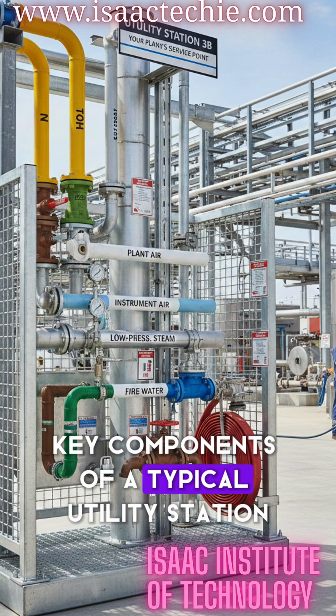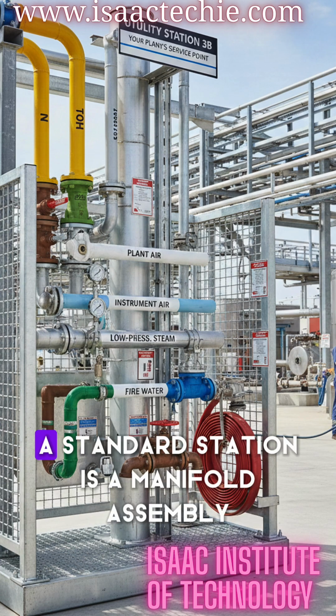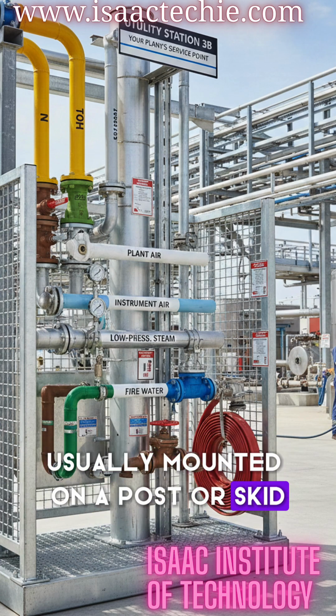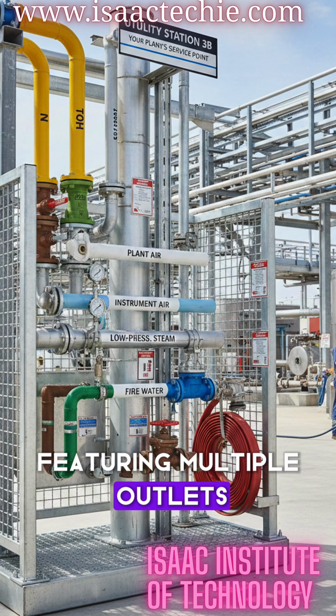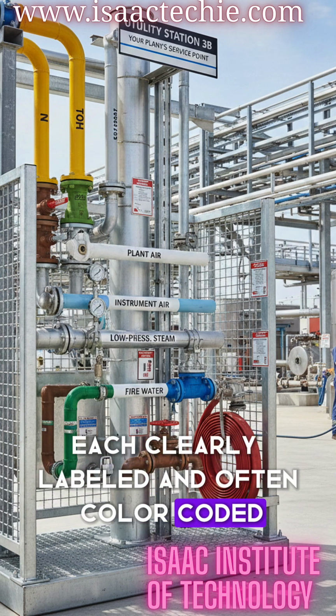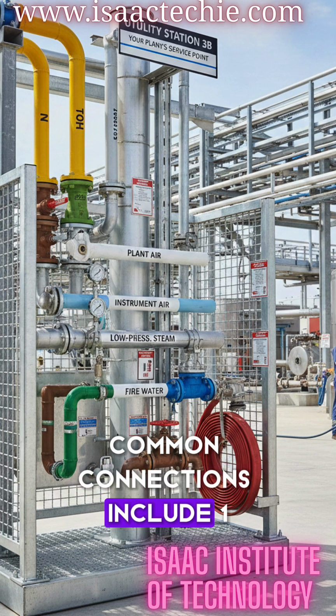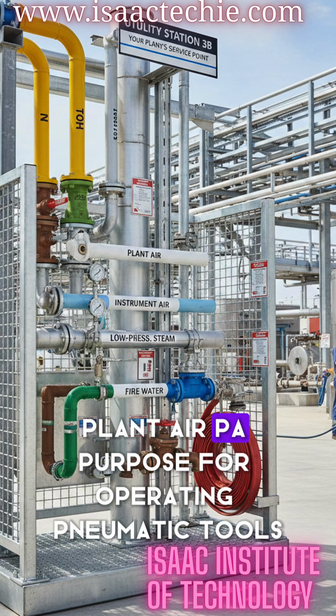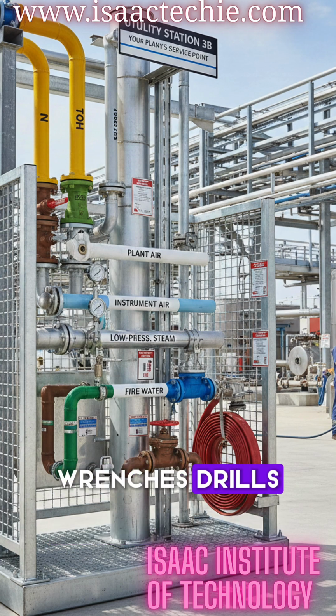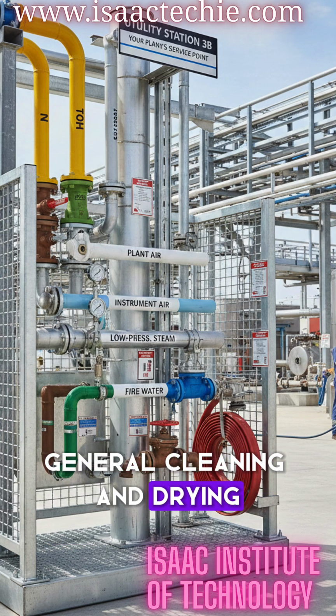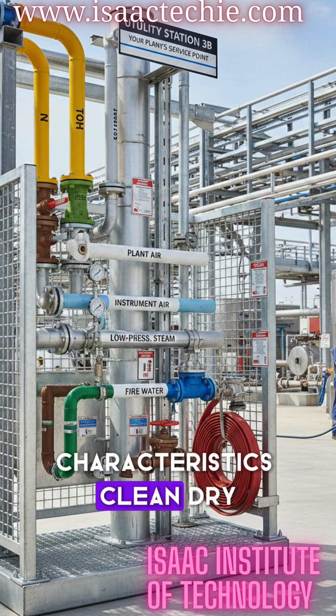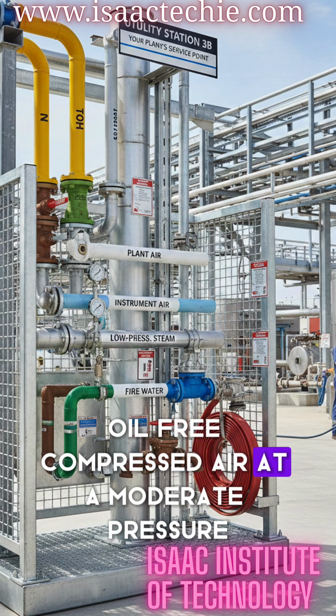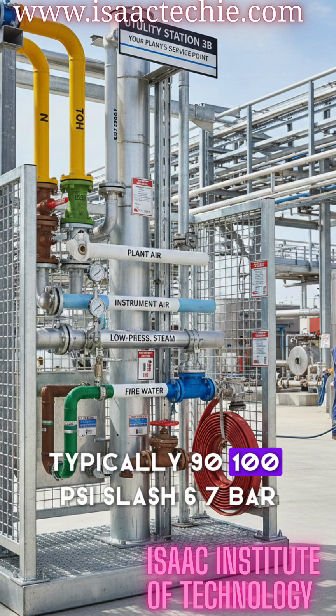Key components of a typical utility station. A standard station is a manifold assembly, usually mounted on a post or skid, featuring multiple outlets, each clearly labeled and often color-coded. Common connections include: 1. Plant air, PA. Purpose: for operating pneumatic tools, wrenches, drills, general cleaning and drying. Characteristics: clean, dry, oil-free compressed air at a moderate pressure, typically 100 psig / 6.9 bar.